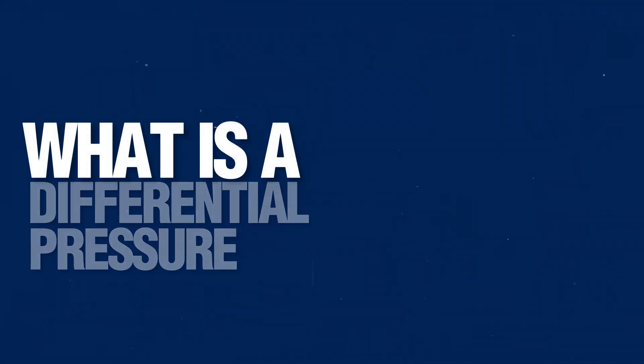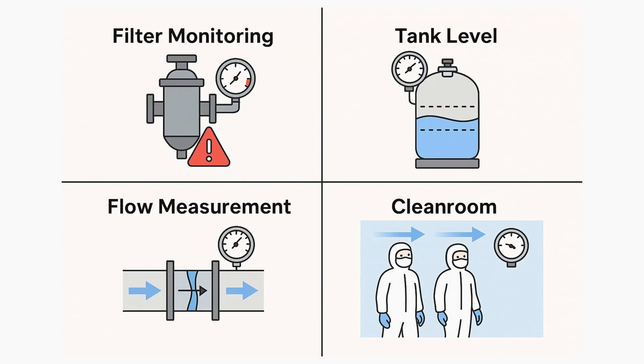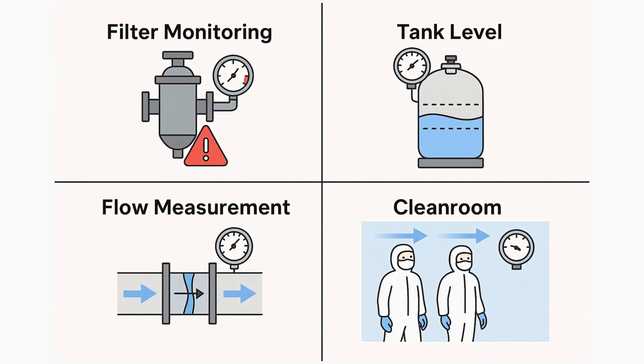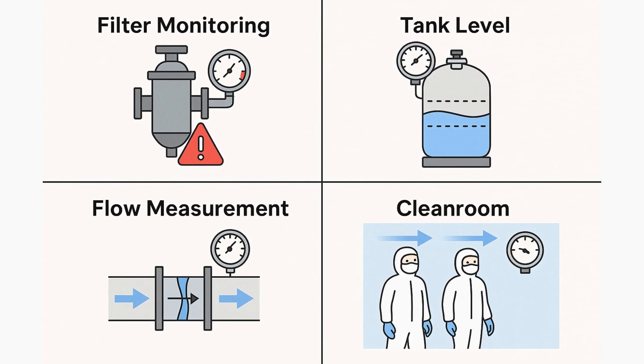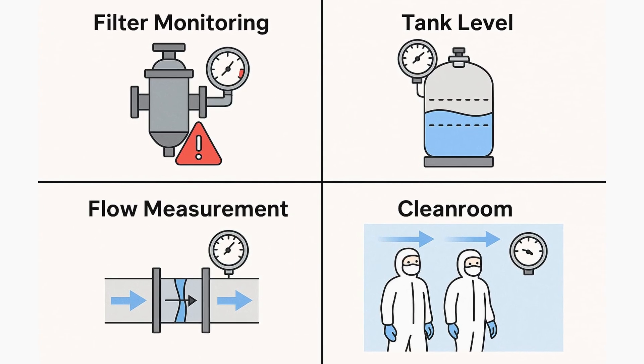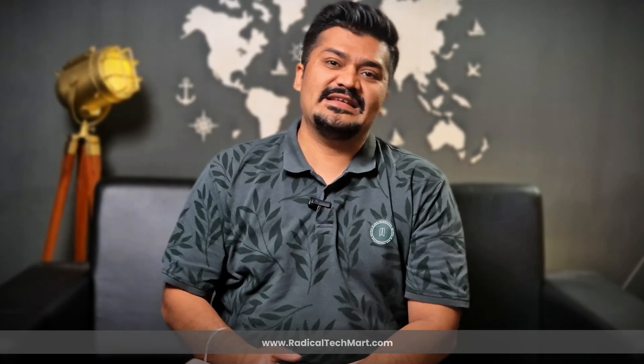A differential pressure gauge measures the difference between two pressure points in a process. It doesn't just show one pressure reading — it shows the pressure difference, which is crucial in many applications like monitoring filters and strainers, measuring liquid level in pressurized tanks, calculating flow across an orifice plate or restriction, ensuring clean room pressure balance, and detecting clogging in HVAC ducts and filters.